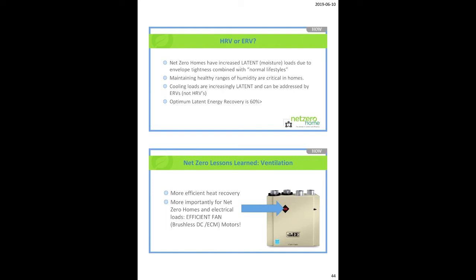The other thing, next step, is we sort of have taken a step back. We've been really concerned that we need like 90% efficient HRVs. We're going to go buy a $10,000 Zehnder and put it in the house because by golly, it's really efficient. Well, here's what we're finding now. It's not so much the heat recovery that we're concerned about with energy efficiency. It's actually the fan motor that's the concern. Here's just a quick example. In general, going from a 65% SRE to about a 90% recovery will reduce about 0.8 gigajoules on a low-load net zero home. So that's pretty good, not bad.